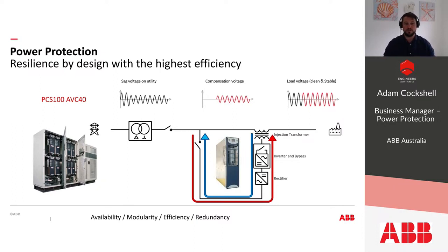It offers plus or minus 10% constant voltage regulation, as well as 100% voltage correction from 60% voltage remaining across 3 phases, back up to 100% for up to 30 seconds, or a single phase sag down to 50% voltage remaining up to 100% for up to 30 seconds as well. Partial correction from 0 volts, correction of all phase angle errors, and correction of utility supply imbalance. More than 90% of financial impact due to power quality events is a result of sags.